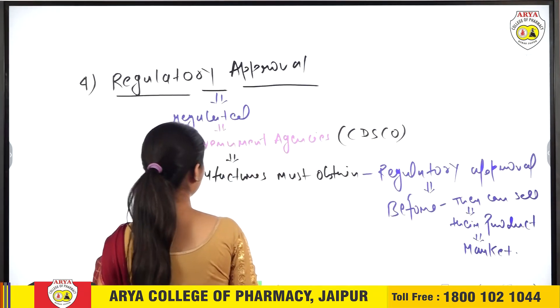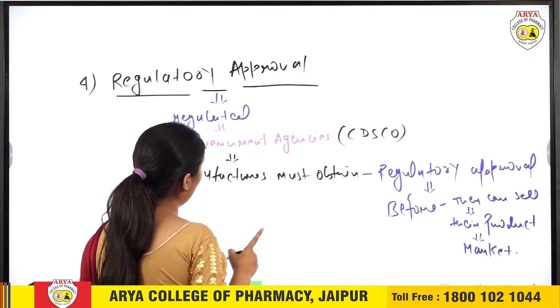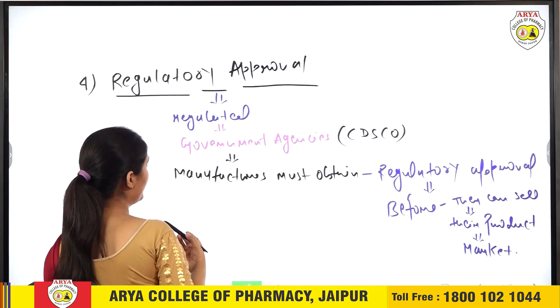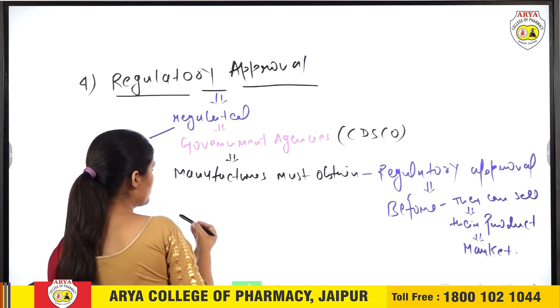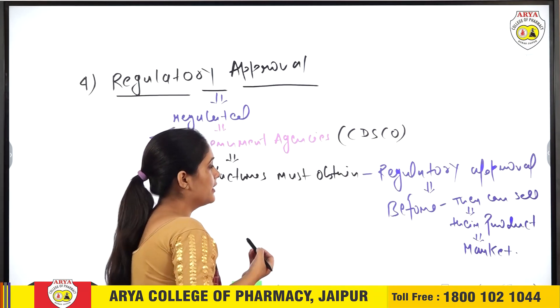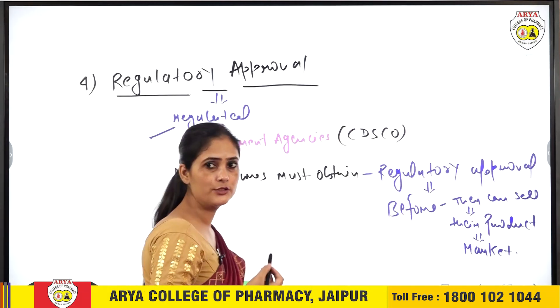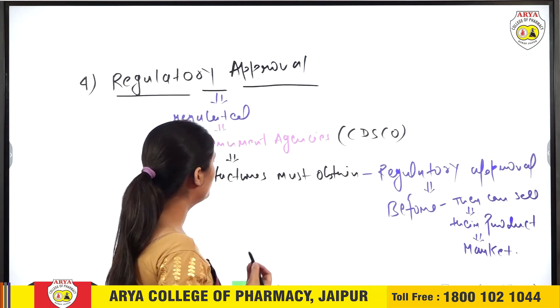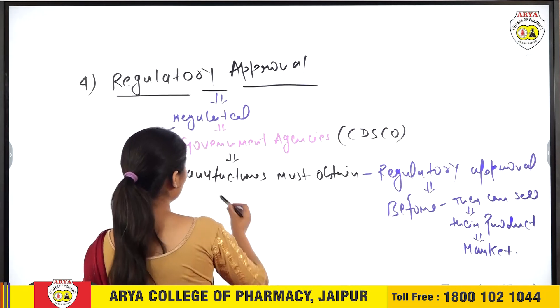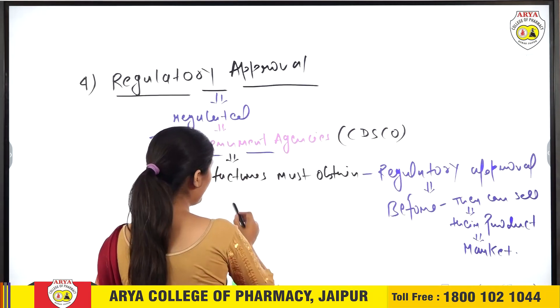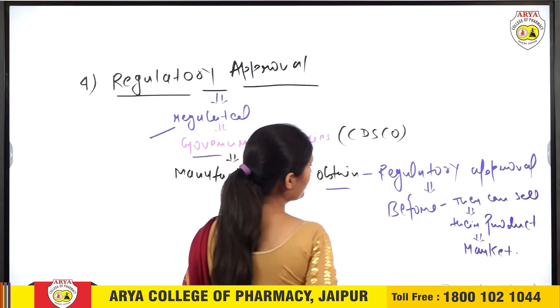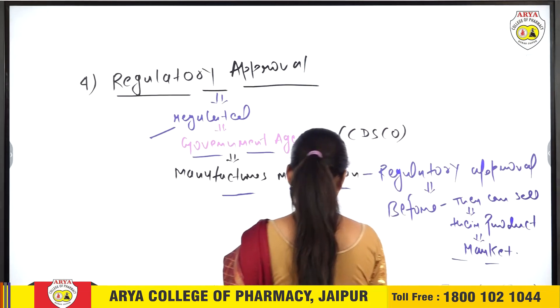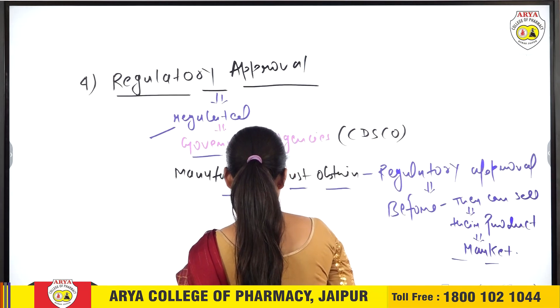Next is Regulatory Approval. Medical devices are regulated by a government agency called CDSCO — Central Drug Standard Control Organization — which has been established to regulate medical devices in a proper and uniform way. Manufacturers must obtain regulatory approval before they can sell their products to the market.